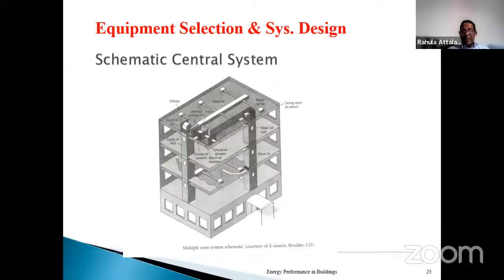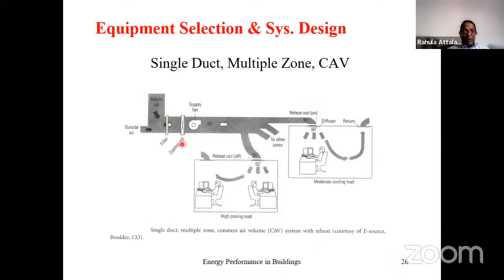This is a typical air distribution inside. And as I said, coldness can be transferred to the circulating air, and the air can be distributed to different zones. For example, like this. So we have a single duct catering to multiple zones, but it will be a constant air volume system. This configuration indicates the air will be supplied at a constant volume. But if the load is higher, then at this point you need a lower temperature. When the load is lower, you need a higher temperature. So constant air volume ensures that the air volume rate is constant, but the supply temperature will have to be varied. Therefore, your cooling coil will have to be adjusted to suit the lower requirement.